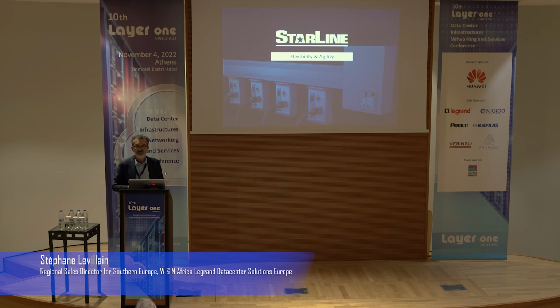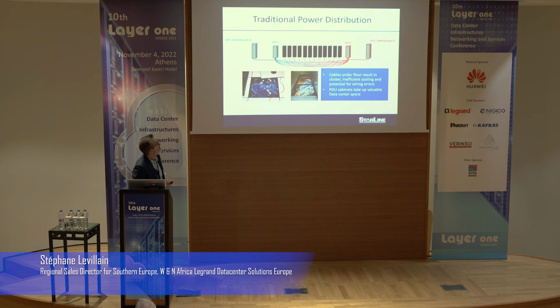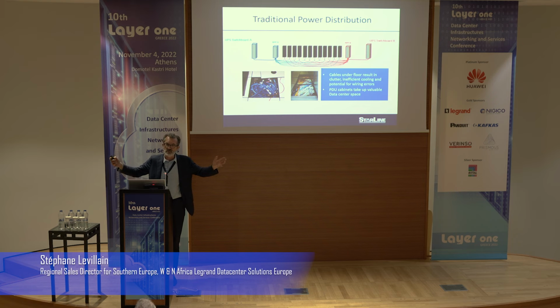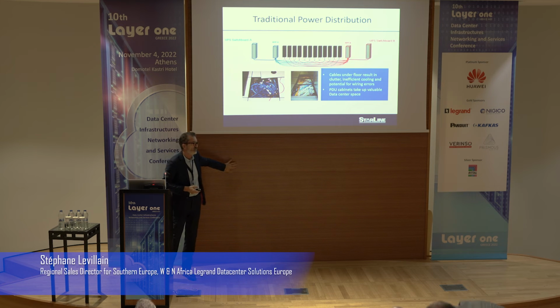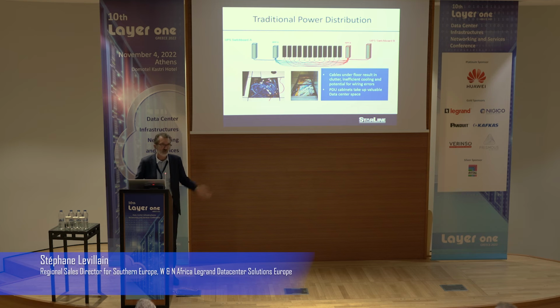And then it makes a good transition with the flexibility and agility. So you know the traditional legacy power distribution, we use UPSs. We still are using UPSs in the new design, but UPSs are feeding PDU cabinets. Mainly the cabinets are in the IT room, close to the wall. And then you have a lot of cables under the raised floor. And you have some issues with the cooling because of the cable. When you want to make some modification, you need to open the tiles. That's not so easy.